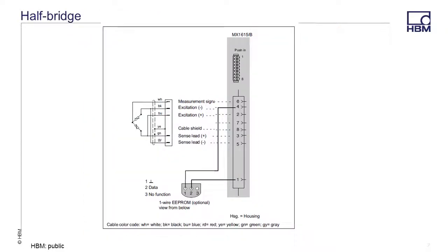Here is the half-bridge wiring schematic for the MX1615B. Take note of the sense lead connections. If your half-bridge wiring cable only has three wires, you must jumper the sense leads at the connector.